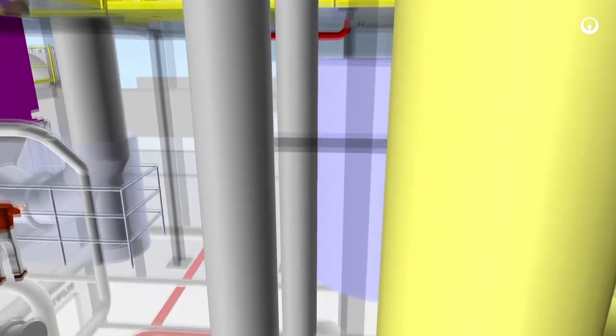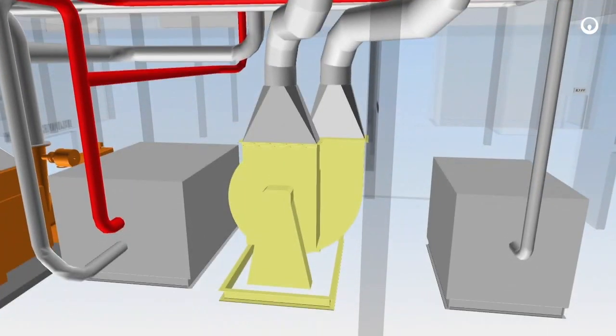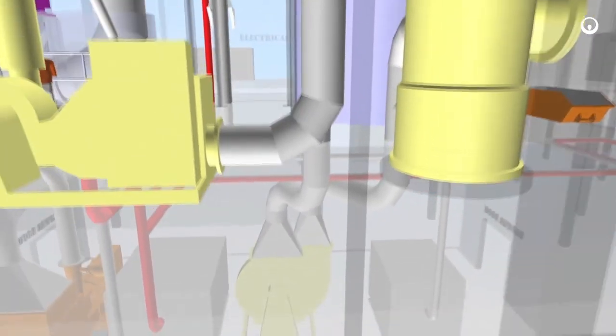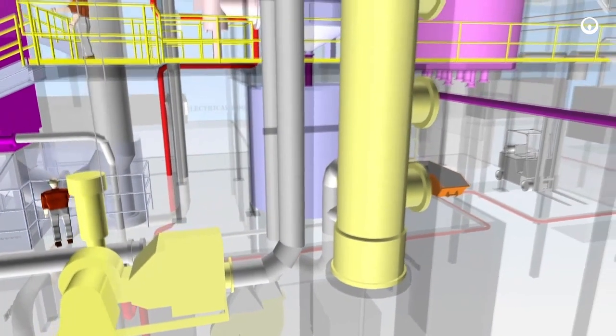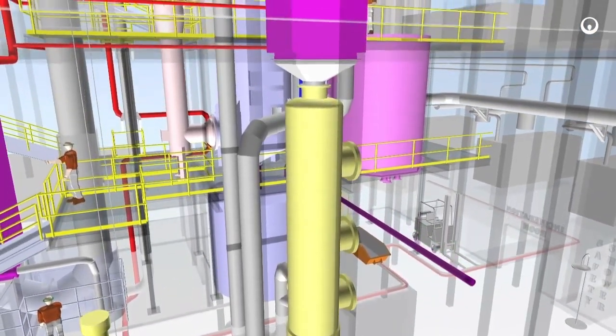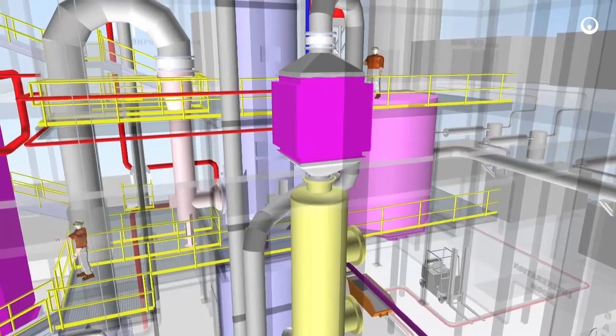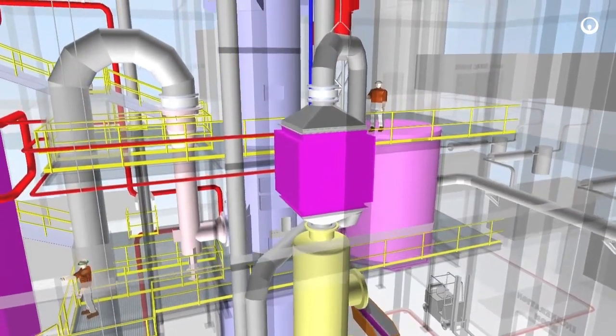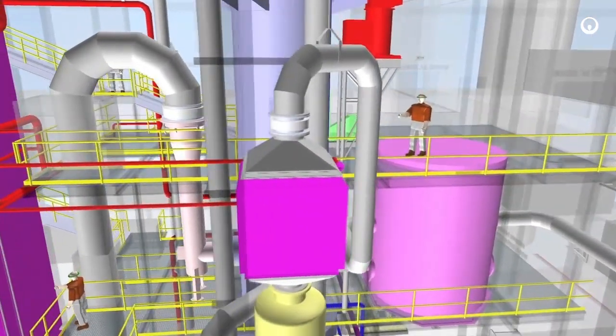Flue gas from the wet ESP travels to the demister for additional moisture removal. It then travels to the coil heat exchanger, where the circulating thermal oil tube side raises the temperature of the flue gas shell side an additional 250 degrees Fahrenheit to reheat the flue gas upstream of the mercury removal system.